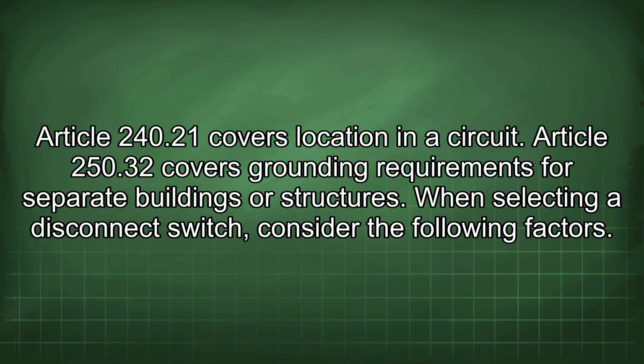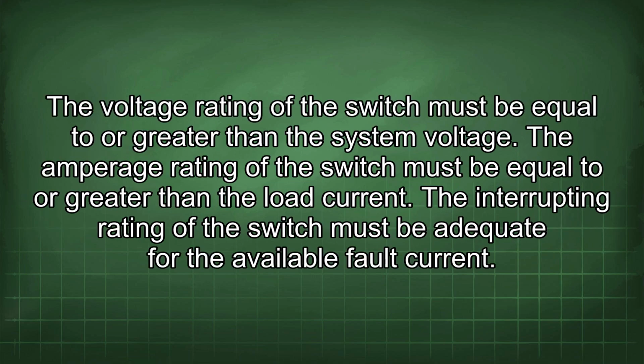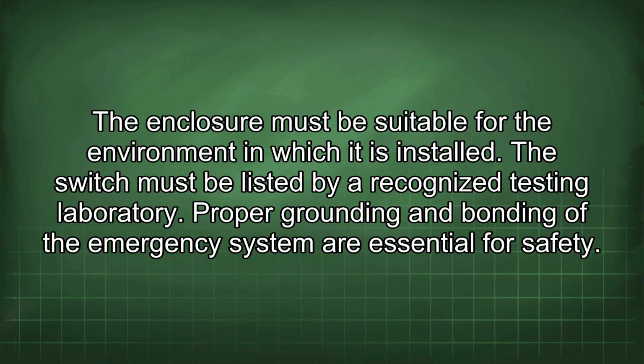When selecting a disconnect switch, consider the following factors. The voltage rating of the switch must be equal to or greater than the system voltage. The amperage rating of the switch must be equal to or greater than the load current. The interrupting rating of the switch must be adequate for the available fault current. The enclosure must be suitable for the environment in which it is installed. The switch must be listed by a recognized testing laboratory.